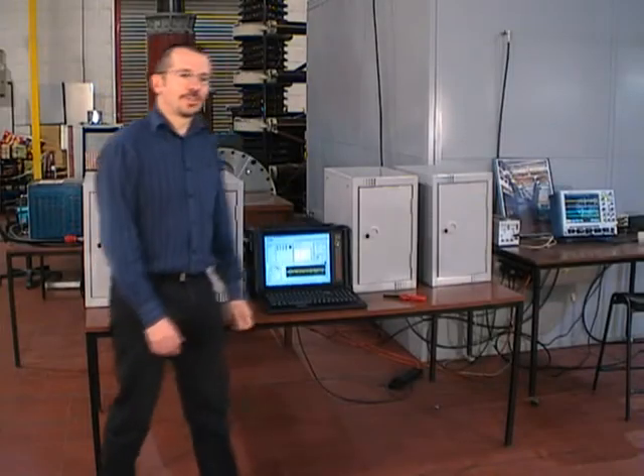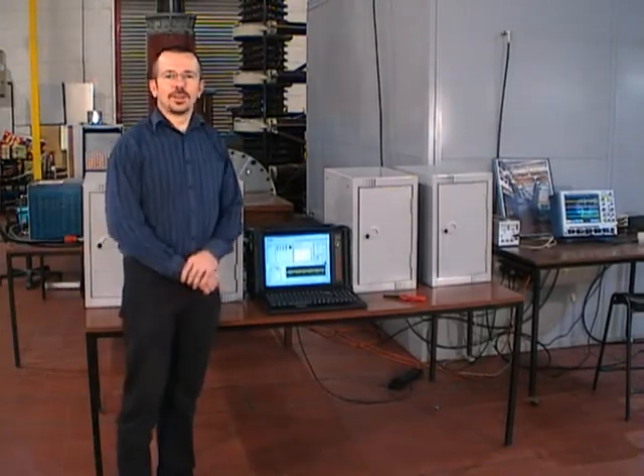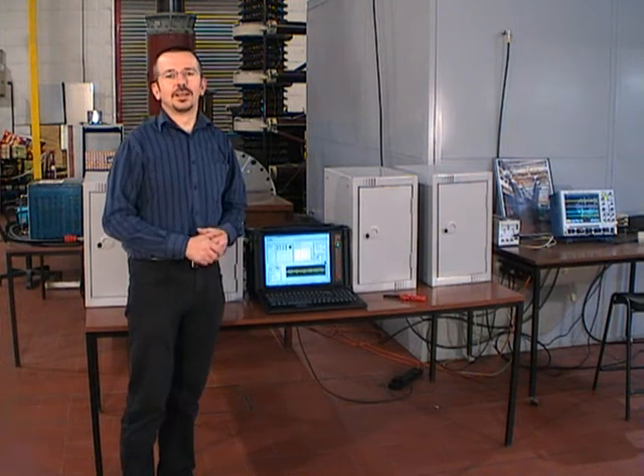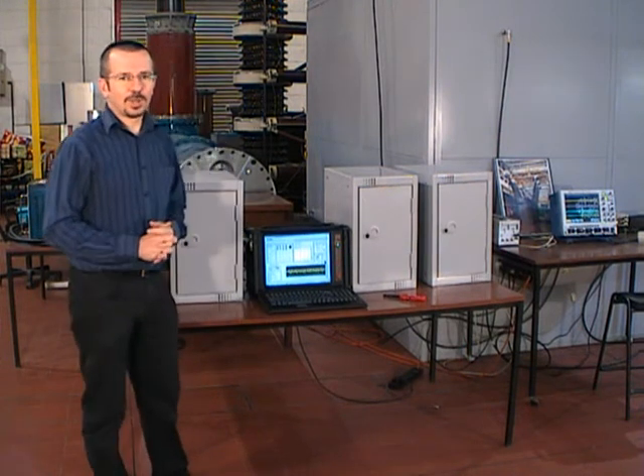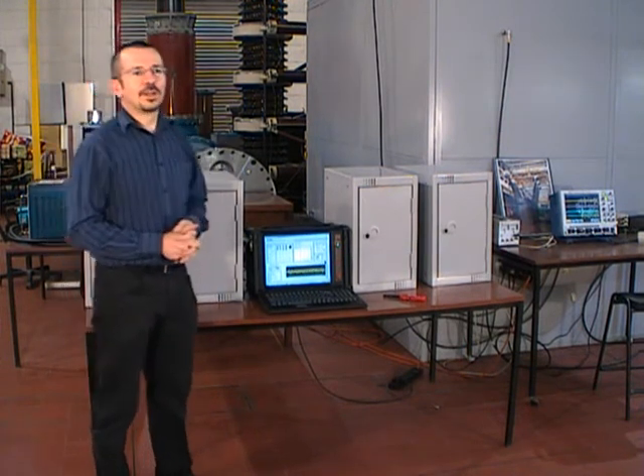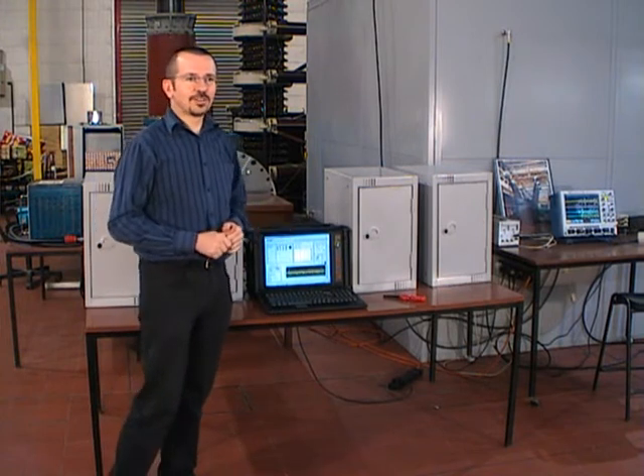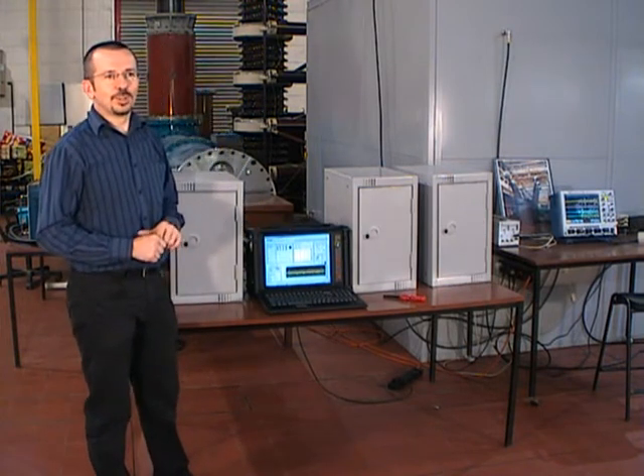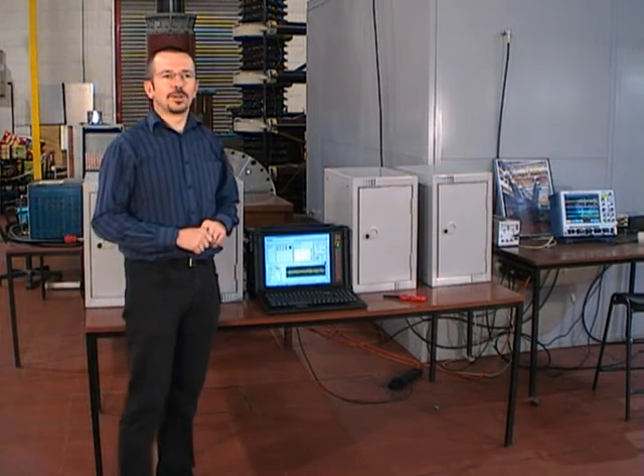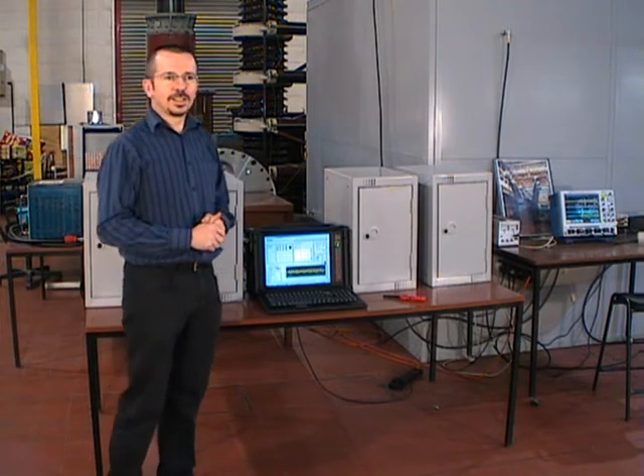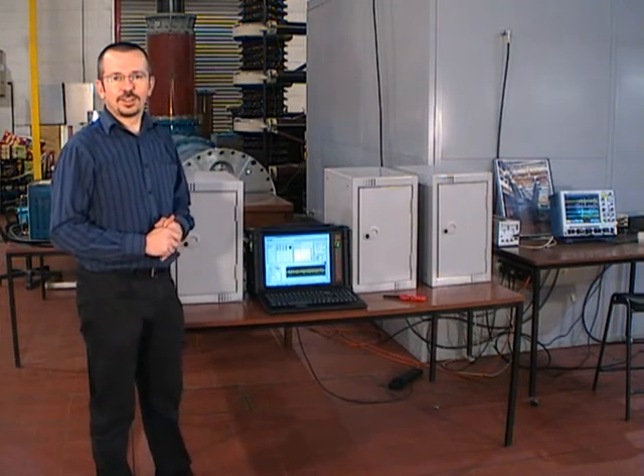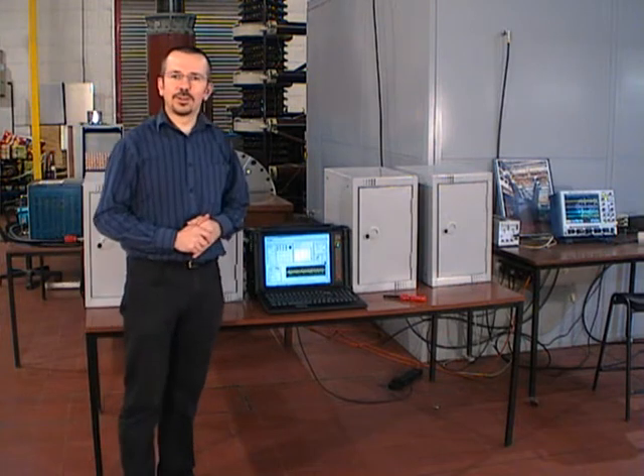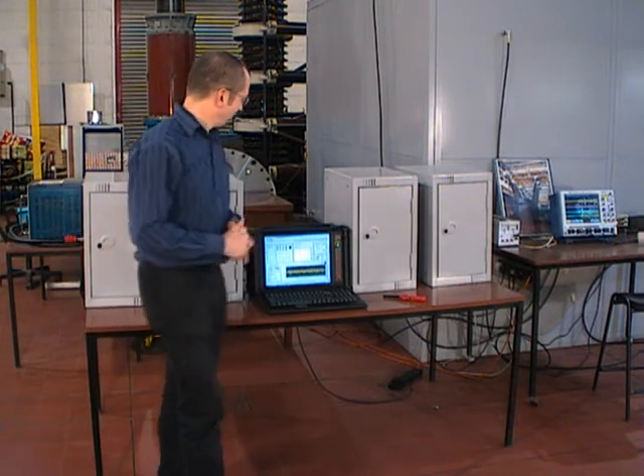Recent monitoring research at Strathclyde has mainly focused on the use of high-speed sampling in a dedicated system to locate partial discharge in transformers. The costs of that type of system are excessive if you get down to distribution level plant, where you might want simpler functionality but some of the same advantages that radio frequency monitoring possesses.